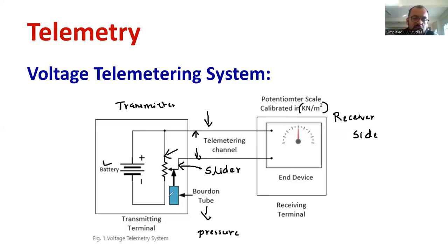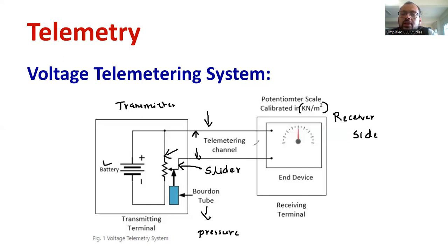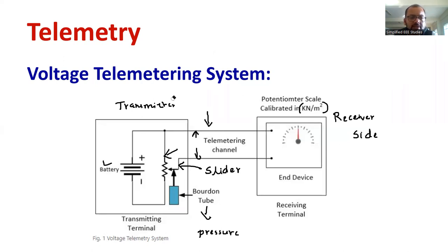With respect to any changes in the Bourdon tube, any changes in the pressure that are directly connected with the Bourdon tube, the information will be transmitted through the telemetry channel and will reach the receiving end side. At the receiving end side you can see a voltmeter calibrated in terms of pressure, giving the equivalent reading of pressure. The pressure information is transmitted from the sending side to the receiving side. This is exactly how the voltage telemetry system operates.